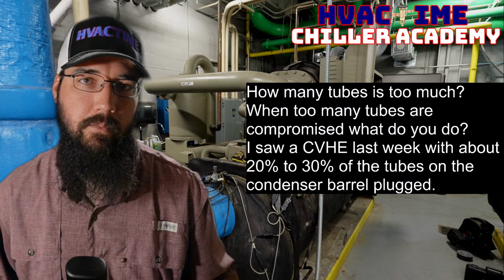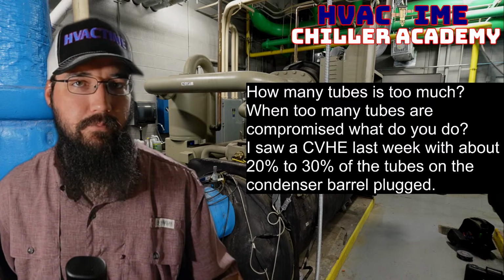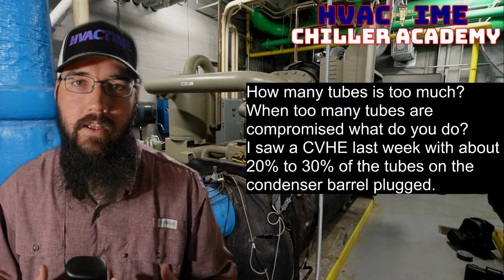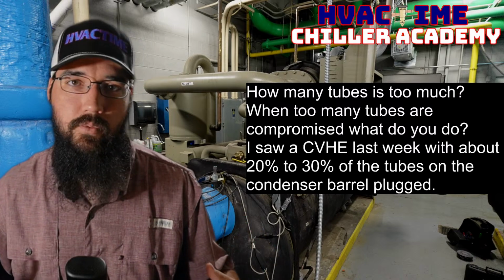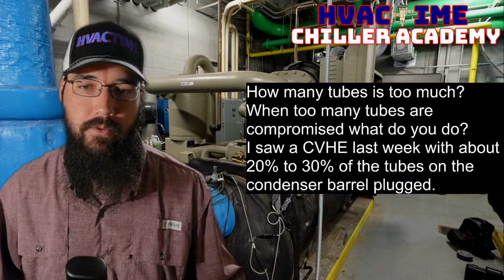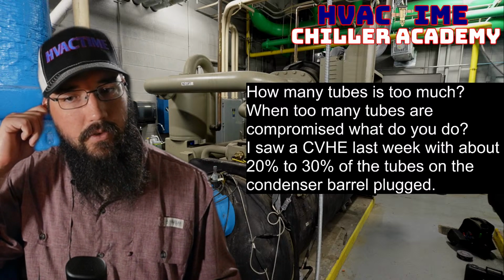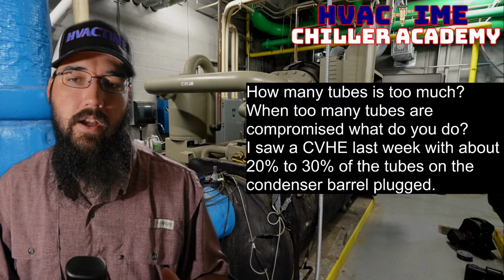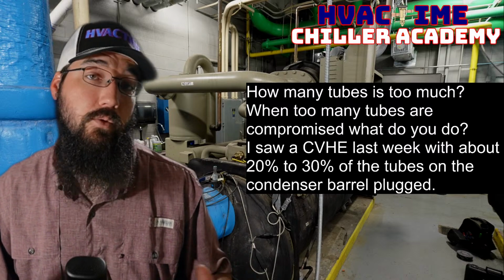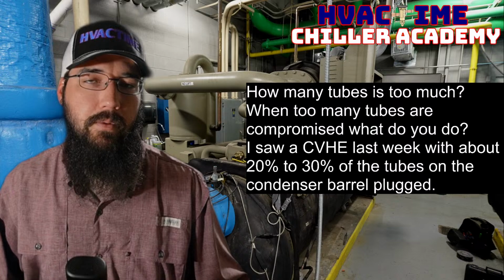So this is going back to, we have a set of condenser tubes that are leaking. They've been diagnosed, whether it be low pressure, high pressure machine, doesn't really matter. And this is not just for the condenser side, but this could be true for evaporator or condenser side, just depending on the circumstances.